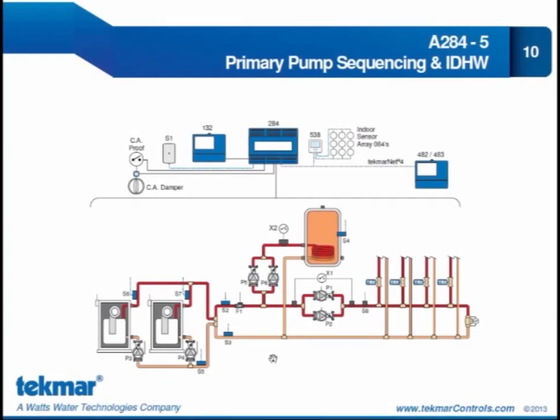Our last application again shows two modulating non-condensing boilers, and these boilers are being operated to provide a boiler target temperature for space heating and for indirect domestic hot water. Again, this indirect domestic hot water is on the boiler system side, so it's IDHW boiler system side location. You can see we have two primary pumps that are being sequenced in a standby operation, and we can also configure the two primary pumps for equal runtime if that is desired. We are proving flow here with a pressure differential switch, even though we do have a flow sensor. So the flow sensor does not have to be used to prove flow. We can use that flow sensor just to monitor flow, which is what we're doing in this case.